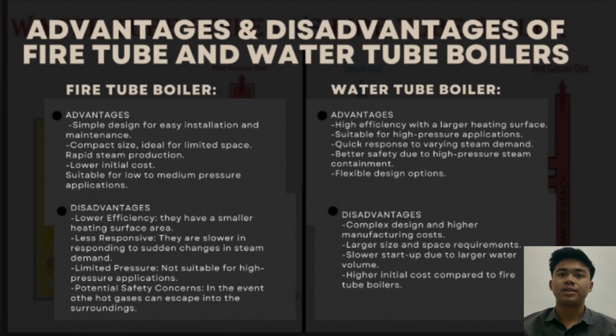Water tube advantages. High efficiency: water tube boilers have a large heating surface area, making them more efficient. High pressure capability: suitable for applications requiring high pressure steam, such as power generation. Quick response: water tube boilers respond quickly to changes in steam demand, making them ideal for variable load applications. Better safety: they are generally considered safe due to the ability to contain high pressure steam. Flexible design: water tube boilers come in various configurations and can be adapted to different needs.